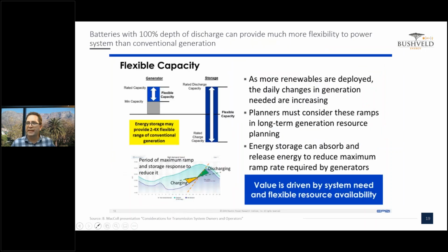Looking at capacity, the same power plant can provide - if you've got a gas generator, you have to run it between a minimum and rated capacity, and it's just generating. With storage, you're getting almost 4 times the amount of grid effect that the battery can do, because of its ability to both charge and discharge at full power. That can be used for ramp rate smoothing, providing basically double its capacity to the grid on demand, versus a gas generator which has to run between a minimum capacity and its rated value.